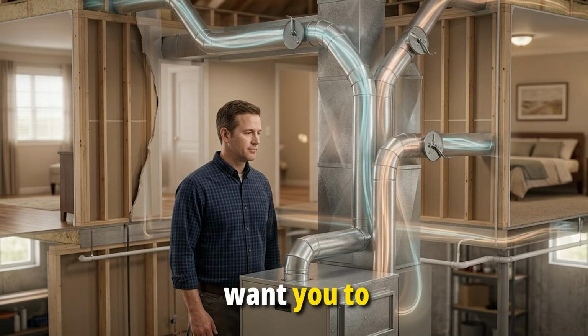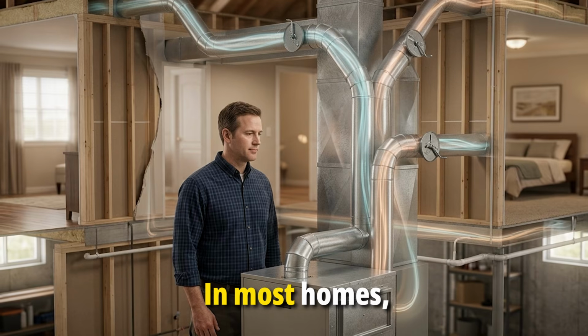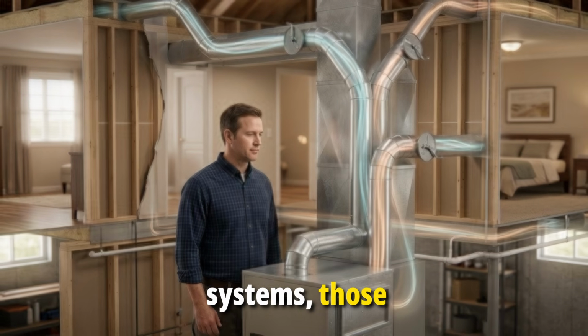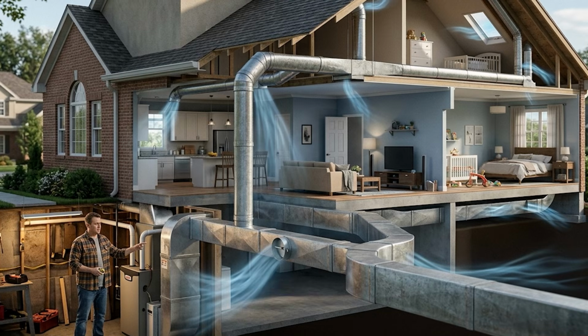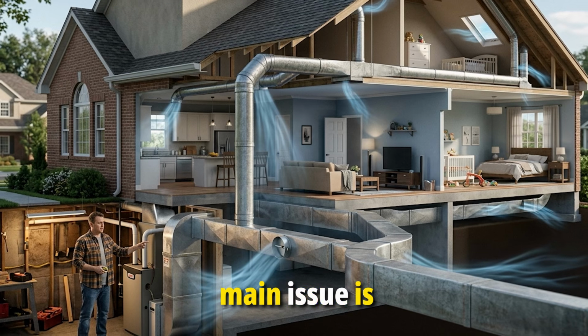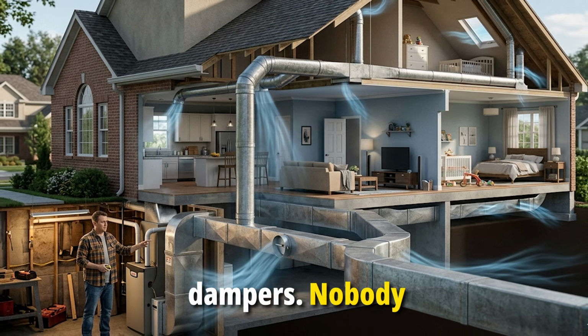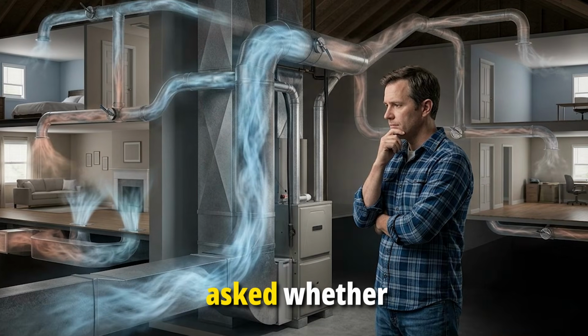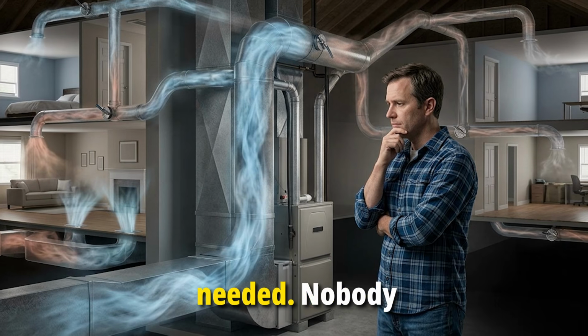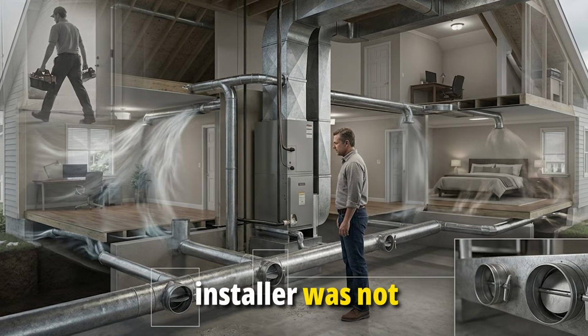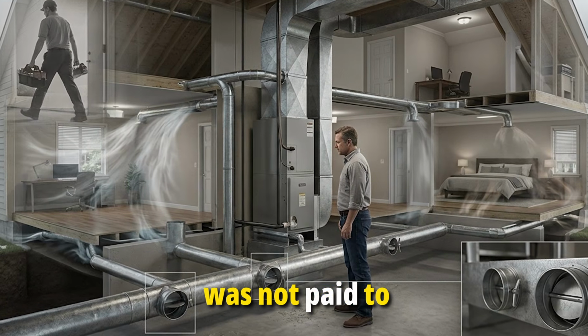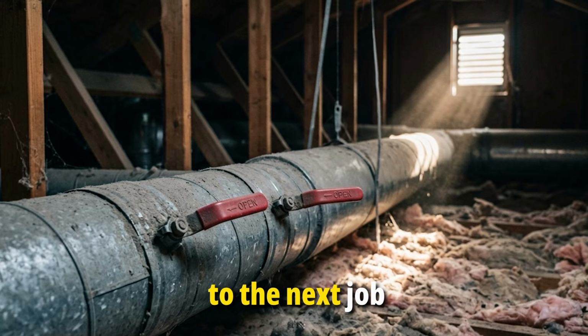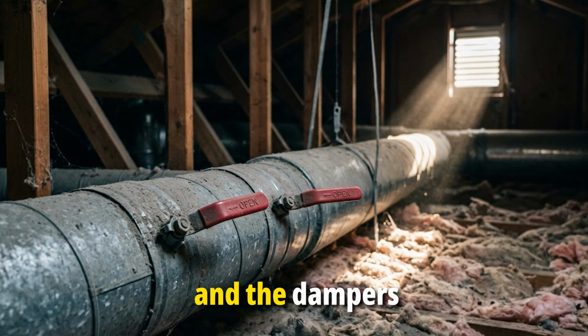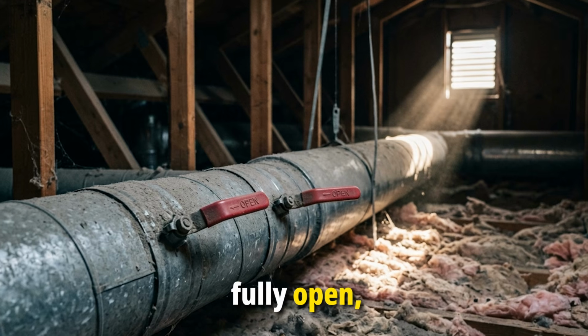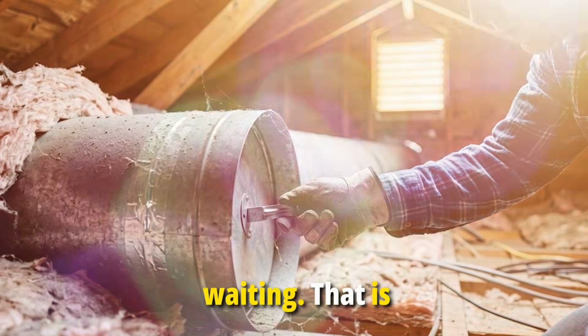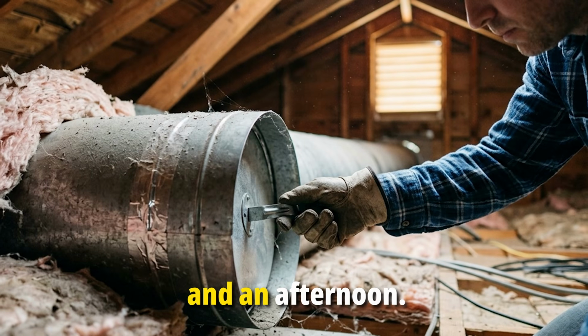But here is what I want you to hold on to. In most homes, ordinary homes with ordinary systems, those expensive problems are not the main issue. The main issue is simply that nobody ever adjusted the dampers. Nobody ever asked whether the airflow was going where it was needed. Nobody balanced the system. Your installer was not trained to do it, was not paid to do it, moved on to the next job the day yours was finished, and the dampers have been sitting there ever since, fully open, waiting. That is a $14 fix in an afternoon.